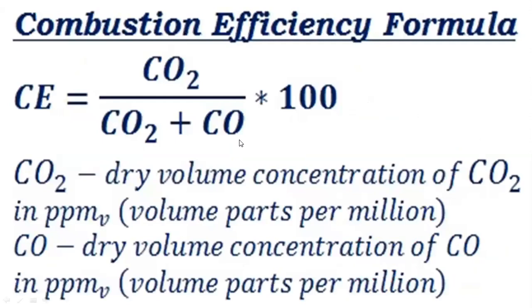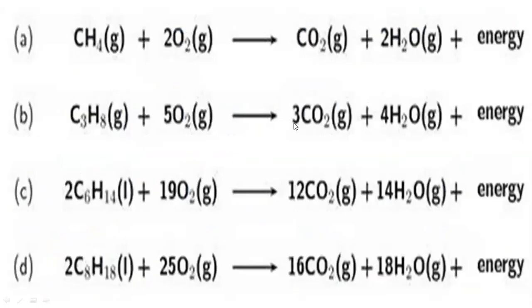Combustion efficiency can be estimated by measuring carbon dioxide and carbon monoxide, or alternatively as heat out divided by heat in. Just by measuring CO2 and CO we can arrive at combustion efficiency. Different fuel combinations require proportionate amounts of oxygen to develop energy. The more dense the fuel, the more oxygen it requires, resulting in more carbon dioxide and more energy. Different fuels have different levels of oxygen requirement for producing heat and energy.